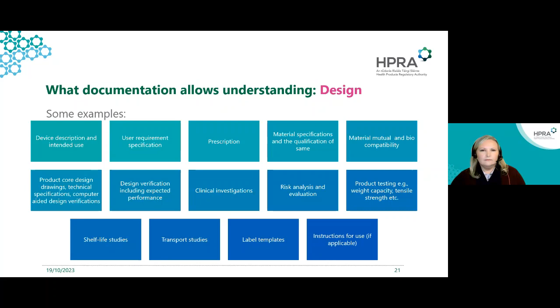Otherwise, documents such as technical drawings, computer-aided design inputs, and verification of those, material selection, and biocompatibility where required, could all be used to demonstrate that a device is designed in a way that is compliant with the general safety and performance requirements and to the broader requirements to comply with the regulation. Other elements such as the prescription and associated available customizations should be part of the documentation along with things like shelf life studies, label templates, and other things like that.